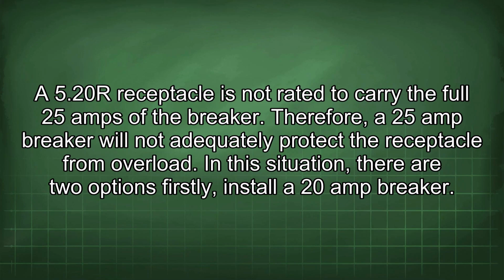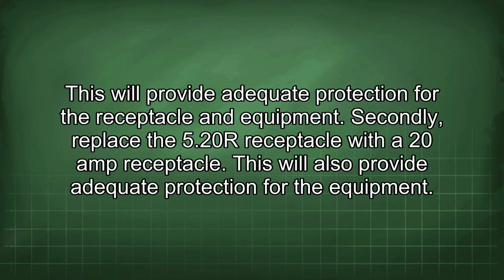5.20R receptacle is not rated to carry the full 25 amps of the breaker. Therefore, a 25 amp breaker will not adequately protect the receptacle from overload. In this situation, there are two options. Firstly, install a 20 amp breaker. This will provide adequate protection for the receptacle and equipment.